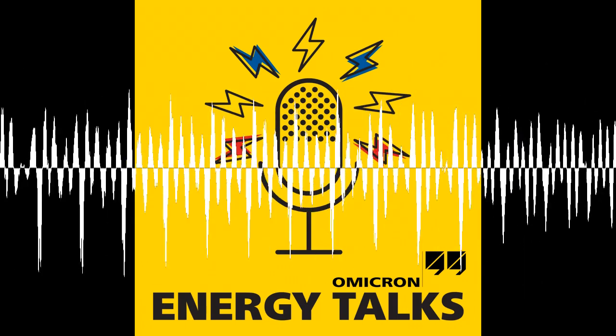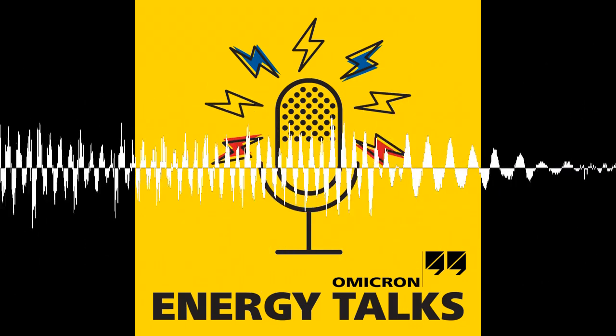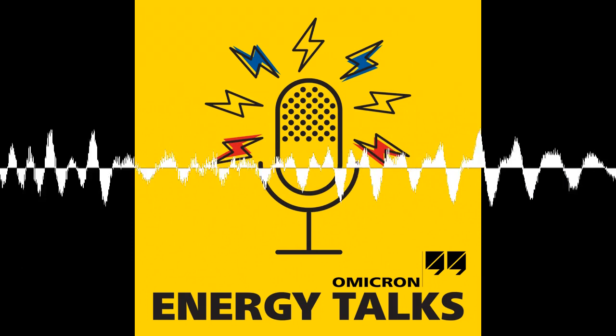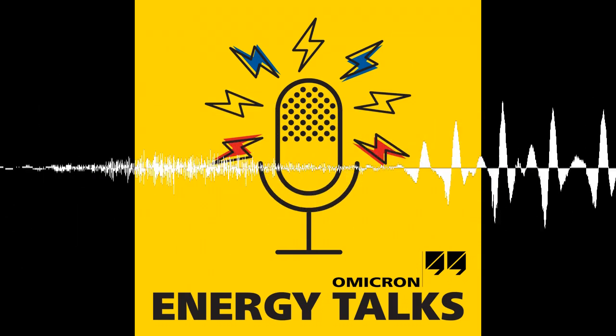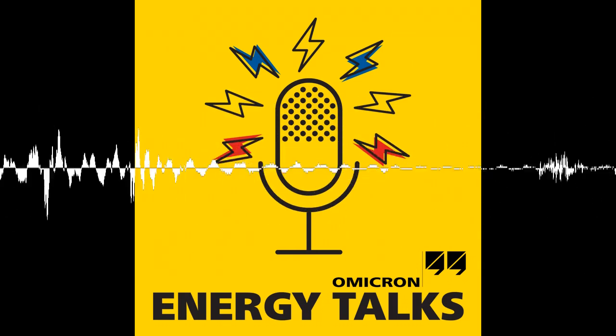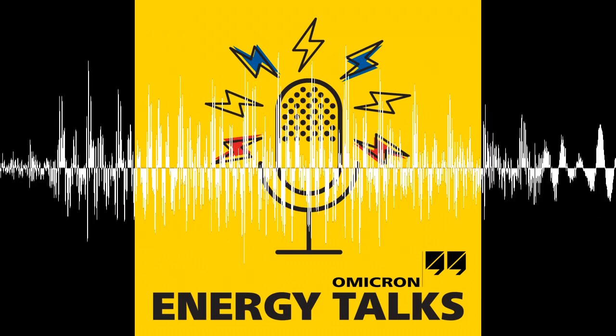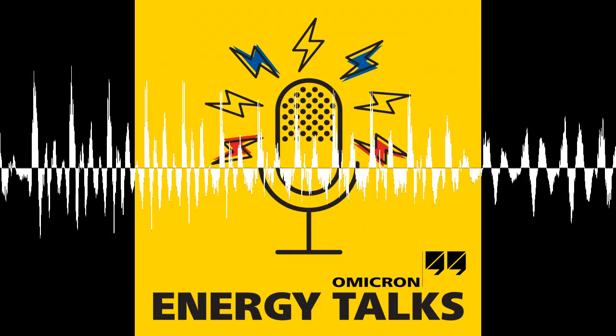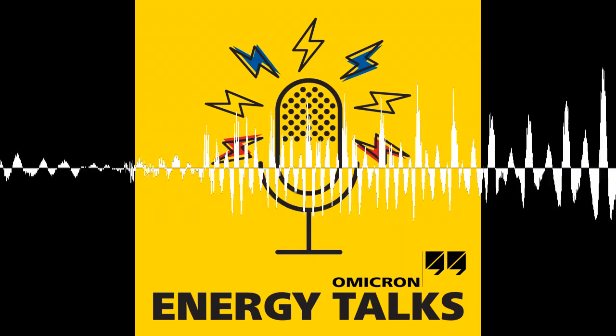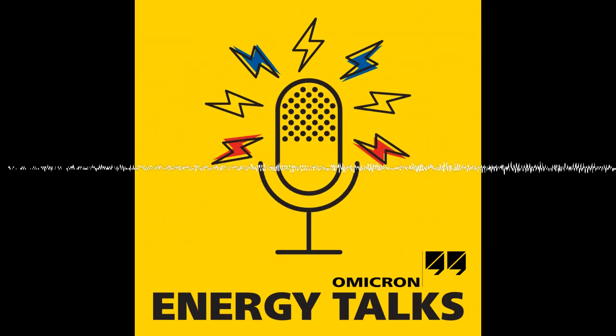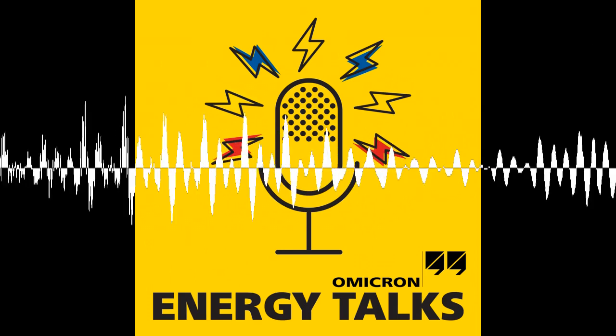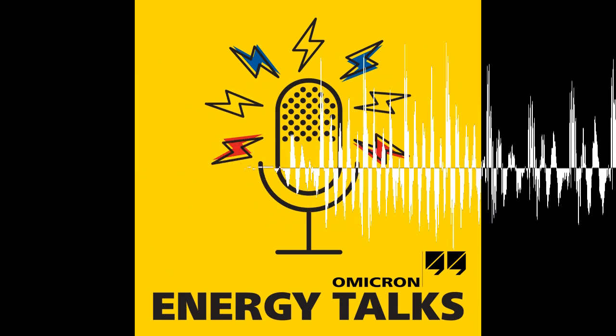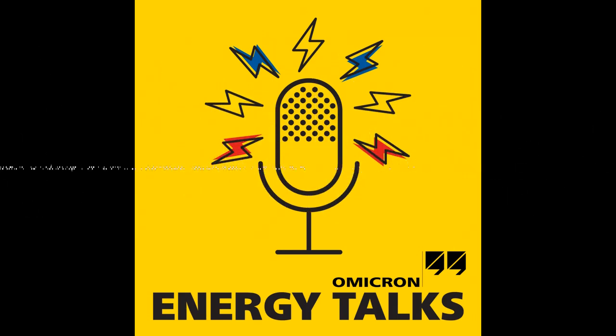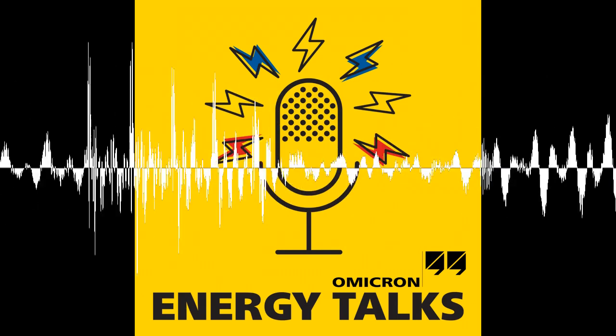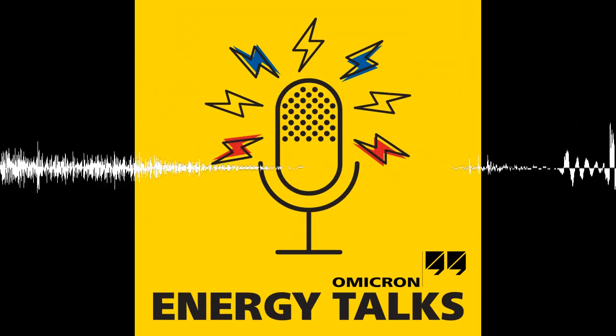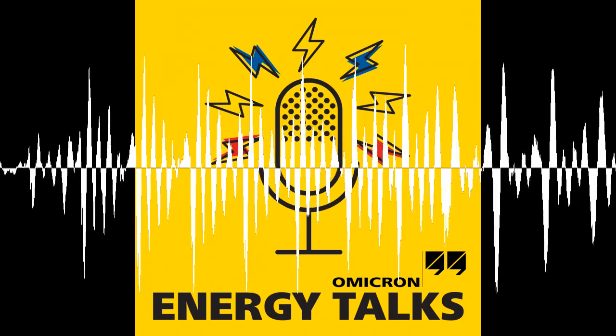Free monitoring in a way, I guess, because the capability is already there, the circuitry is already connected, and it just requires the engineers of the utilities to make the programming to capture that data. I mean, for monitoring, I wouldn't trust it too much since you don't have any information about the main contact. They could fall off and you wouldn't see it in the auxiliary contact, but at least it gives you a feeling about the general operating mechanism, how fast that is going to be. It's super basic, but yeah.